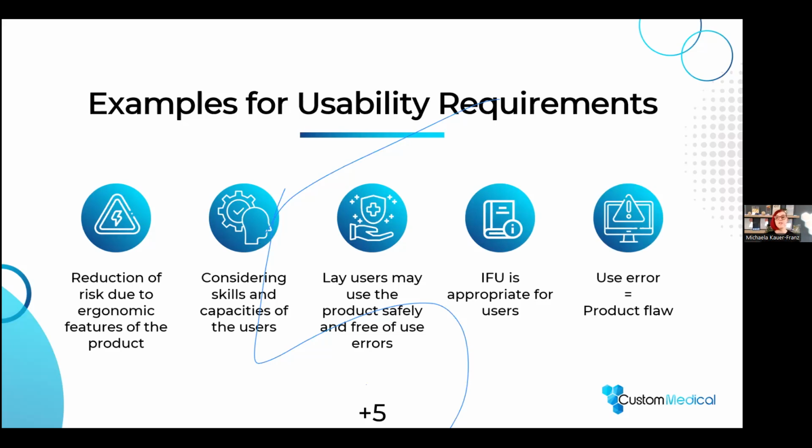And I think one of the very relevant aspects is the definitions aspect, which is named in the MDR. What they say is that depending on the circumstances and everything that you've done so far, a use error which is reported can be seen as a product flaw. So now we are into the question of who is paying money for problems and what is considered a product flaw.